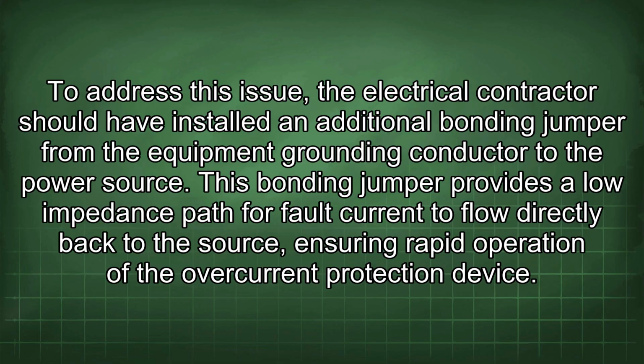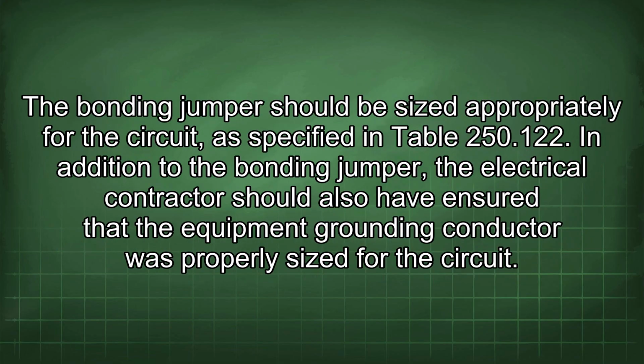To address this issue, the electrical contractor should have installed an additional bonding jumper from the equipment grounding conductor to the power source. This bonding jumper provides a lower impedance path for fault current to flow directly back to the source, ensuring rapid operation of the overcurrent protection device. The bonding jumper should be sized appropriately for the circuit, as specified in Table 250.122. In addition to the bonding jumper, the electrical contractor should also have ensured that the equipment grounding conductor was properly sized for the circuit.